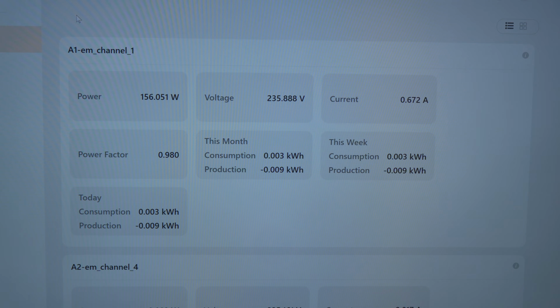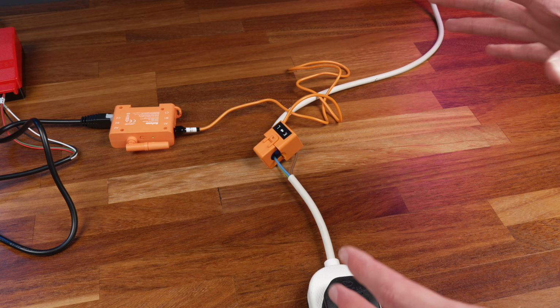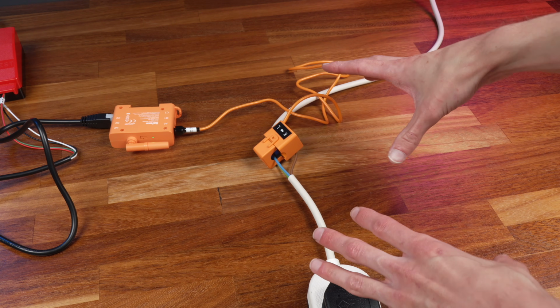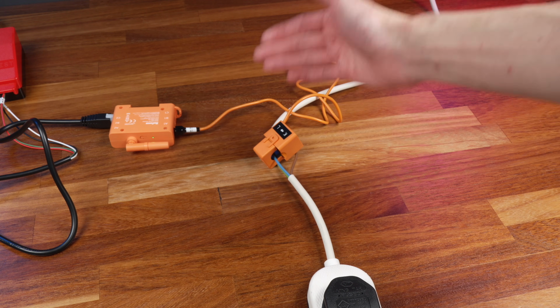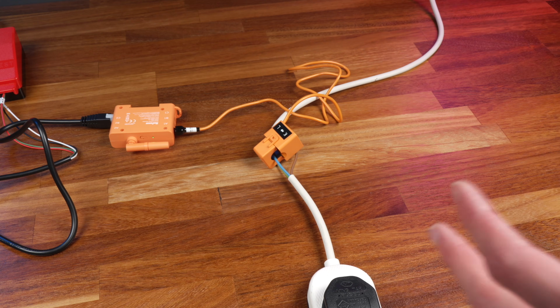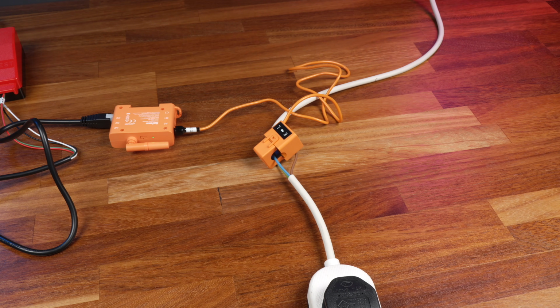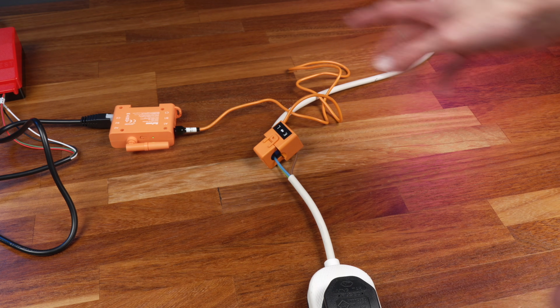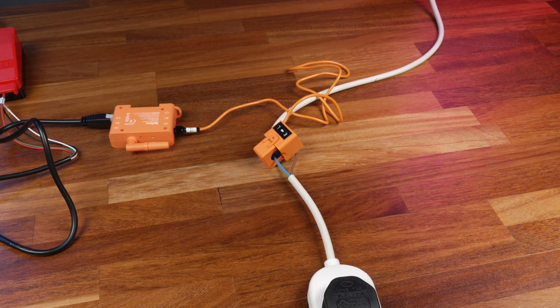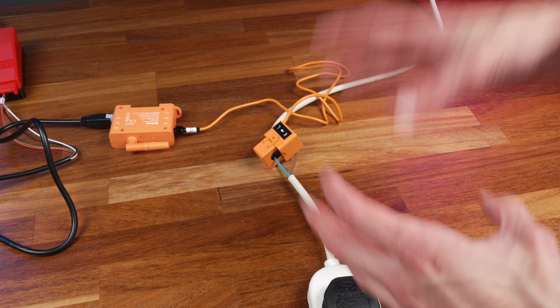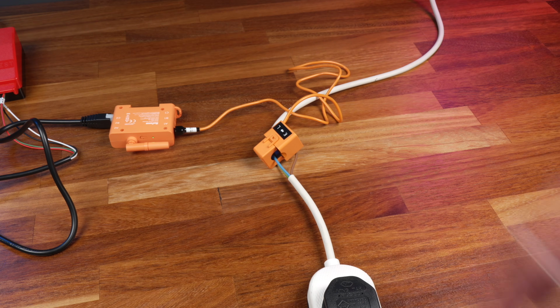and this time we're measuring it on the neutral. It's also worth mentioning, although I don't have a second breakout adapter to demonstrate this, that you can pass multiple wires through the same CT, and you'll essentially just measure the total current flowing through them all. You just need to make sure that the current is flowing in the same direction through all of them, otherwise you'll end up with the currents cancelling each other out, and you need to make sure that you don't go beyond the maximum rating of the CT, in this case 120 amps.